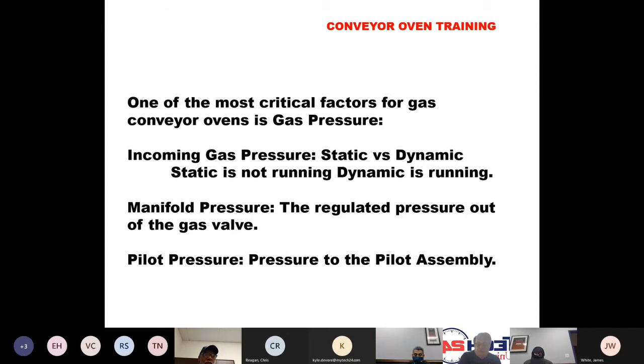Static pressure is the pressure before we turn the appliance on. So I take a manometer, I hook it up to the incoming gas pressure, and before I turn my oven on, that's my static pressure. Once I turn the appliance on, now I have what's called dynamic or running pressure. Typically, I don't want to see more than about a 20% drop between static and dynamic.